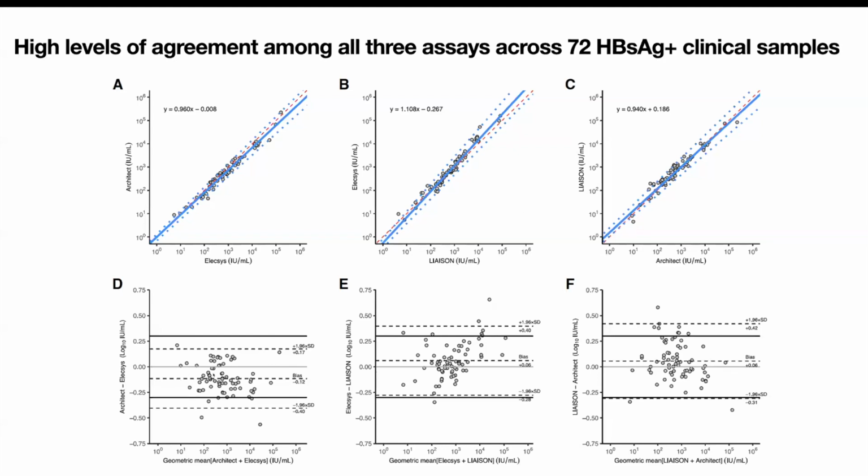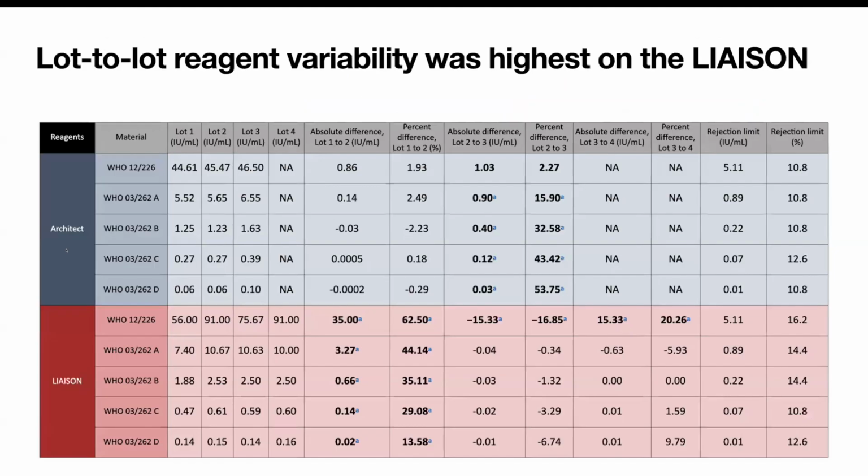And this is to look at the geometric mean difference between these assays. And you can see they're, for the most part, pretty close to that, right at the zero equivalence between the assays. So once you've gone through the trouble of calibrating the assays, running them as they're being run in the reference labs, I'm sure as well, this works out well for the values. You just have to do all the front matter to figure out what is the appropriate linear range that you can do. So that was positive.